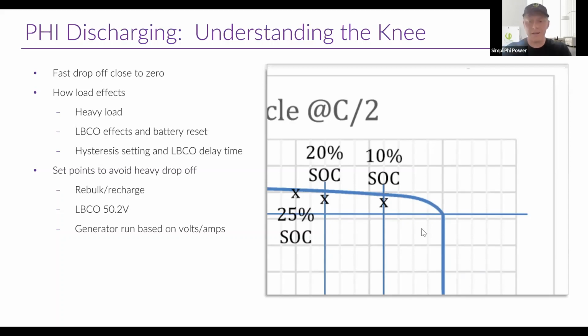So if you've got a very small load on the battery, you may notice that this happens a lot slower. But let's imagine you've got the largest load possible. You've got a C/2 load, and your battery is approaching 0% state of charge, which corresponds to 48 volts. As soon as your battery hits that 50.2 mark, it's going to really start decreasing in voltage a lot faster. And then as soon as it hits that 48 volt mark and it's at 0, it takes very little time to plummet from 48 volts all the way down to 0 volts, completely empty. Very little time. So you've got to be careful here.